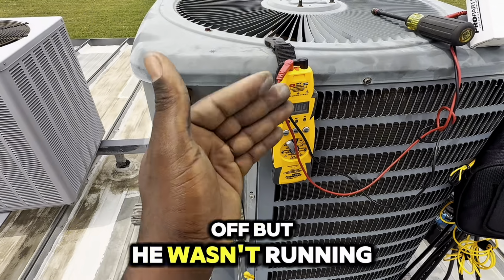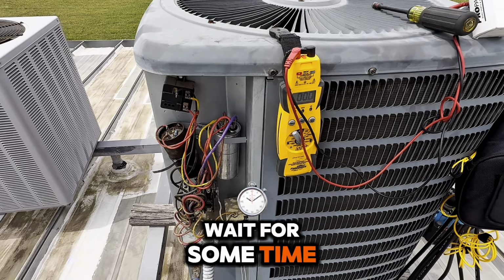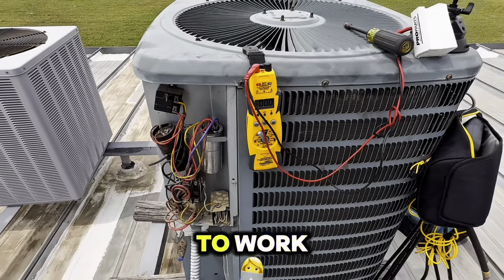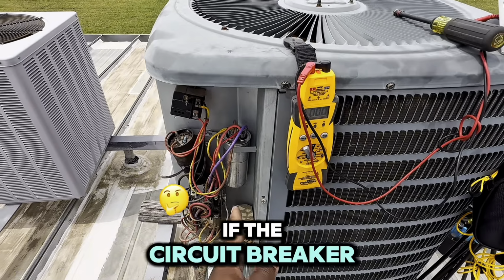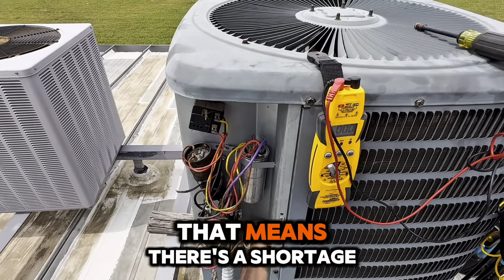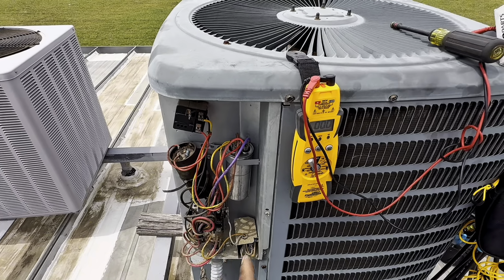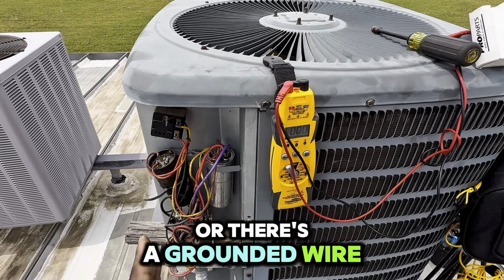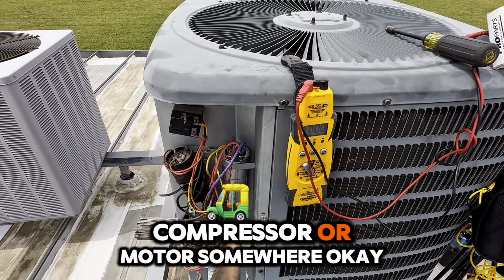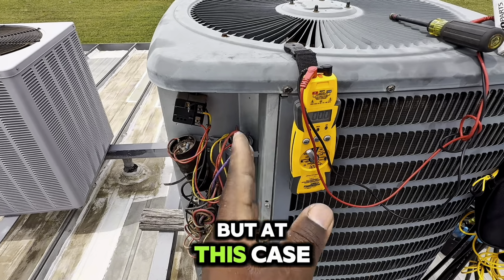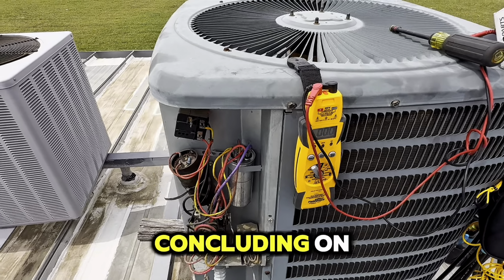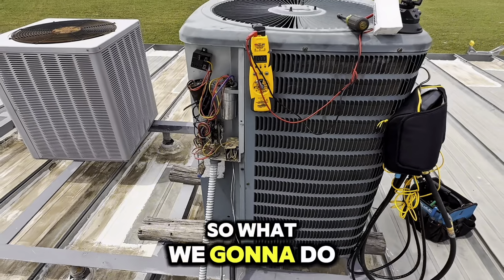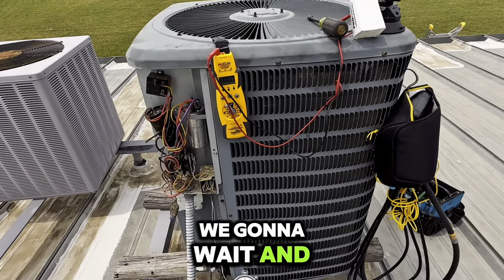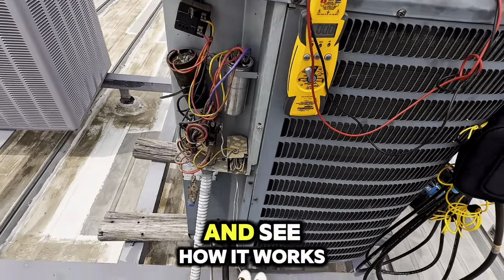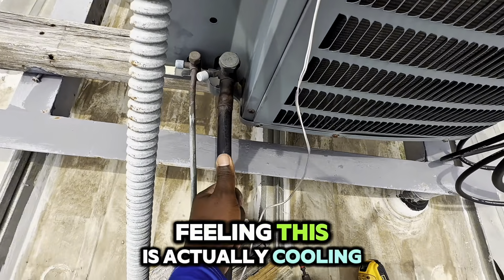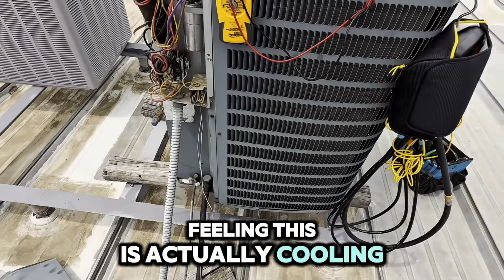But it wasn't running, now it's running. Let's wait for some time and see how it's going to work. If the circuit breaker trips immediately, that means there's a short, or there's a grounded wire, or there's a burned compressor or motor somewhere. Okay, but in this case, that's not what we are concluding on. So what we're gonna do, we're gonna wait for a moment and see how it works. Feeling this, it is actually cooling.